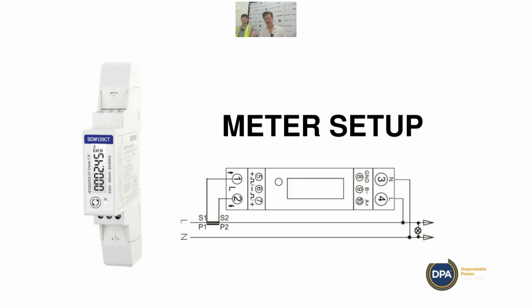What I'd recommend, because people quite often find the meters need a bit of troubleshooting, is put your meter in place, fire it up, then get your multimeter and measure the voltage output on A and B. You should get about 3 volts or so. Then at the other end of your cable, measure it there too, and make sure your A and B are the right way around. If you've got voltage there, it should be talking to the inverter. It's just a quick check to make sure you haven't got a problem in your connections before you start troubleshooting the software commissioning.